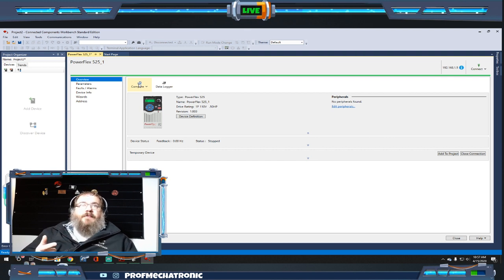You could set up two VFDs to communicate with each other using digital input, digital output. If it was simple logic, like 'when I start, I want you to start' or 'when you stop, I'll stop,' you could do that between two VFDs. There would be some relays involved, because you wouldn't want a direct wire to each other.